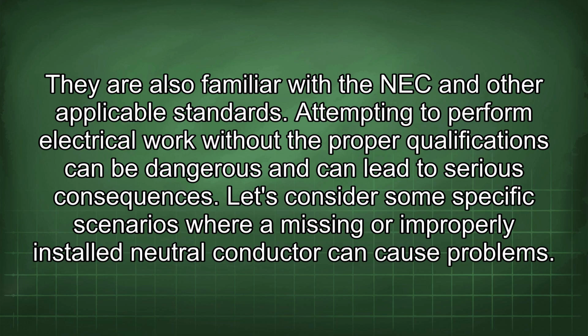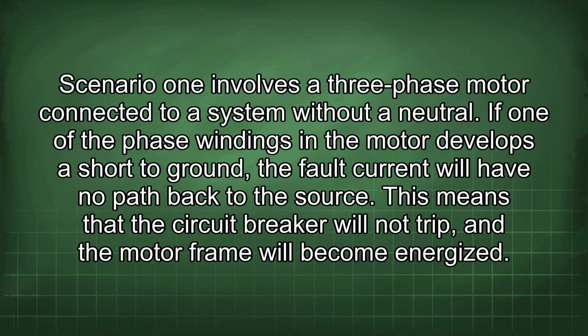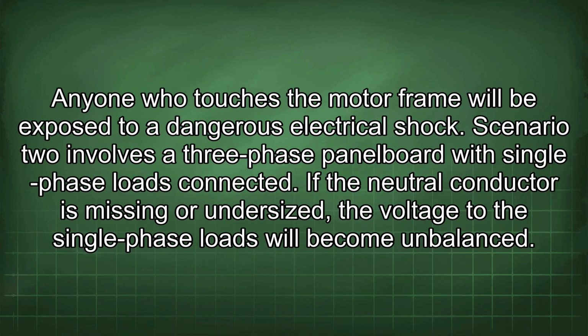Let's consider some specific scenarios where a missing or improperly installed neutral conductor can cause problems. Scenario 1 involves a three-phase motor connected to a system without a neutral. If one of the phase windings in the motor develops a short to ground, the fault current will have no path back to the source. This means that the circuit breaker will not trip and the motor frame will become energized. Anyone who touches the motor frame will be exposed to a dangerous electrical shock.